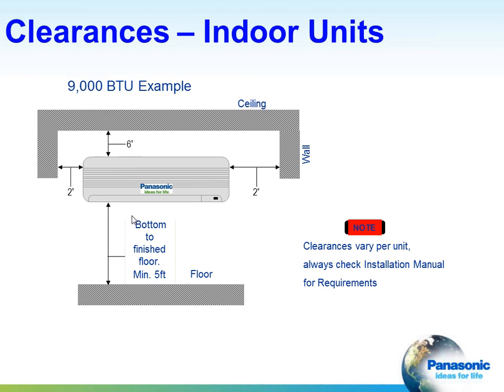On the indoor units, you want to maintain a minimum clearance of 6 inches from the ceiling and then 2 inches from each end. And then, of course, you want to be somewhat off the floor by a minimum of 5 feet. And go to each of the individual installation manuals for any given system for the particular requirements.